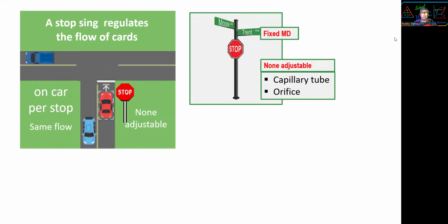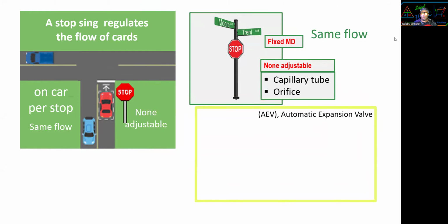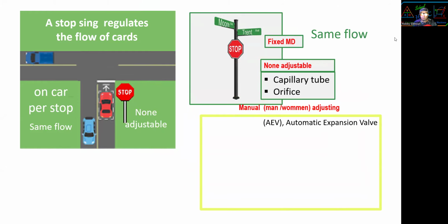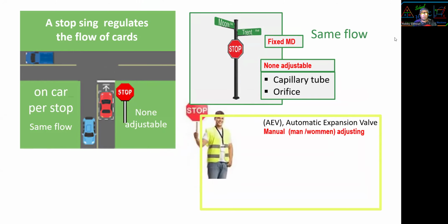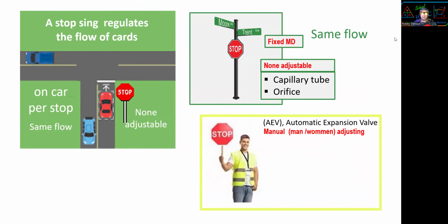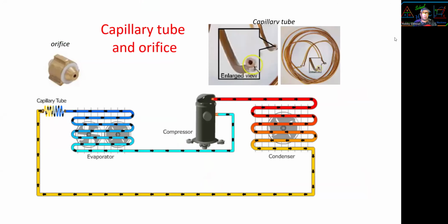Okay, next. There are fixed metering devices. Same flow. The automatic expansion valve, manual adjustment. You can adjust it one time and leave it, like a person holding a stop sign. Sometimes stop, sometimes no stop. But you can adjust it. A qualified service technician needs to adjust the boiling point on the evaporator using a PT chart. I will cover that later.